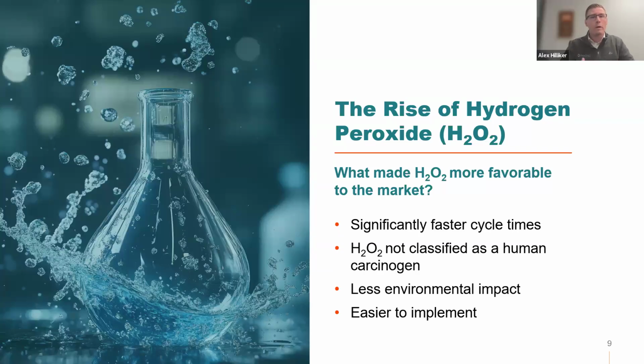And so, people may wonder what made hydrogen peroxide a more favorable option to ethylene oxide. First and foremost, one thing we always like to point out is that cycle time really matters here. With ethylene oxide, it used to take 8, 10, 12 hours to sterilize one load. And that's because of all of the requirements that were put in place for ETO. You've got a precondition, you sterilize, you aerate. That took a really long time. Today, with modern H₂O₂, vaporized H₂O₂ and H₂O₂ gas plasma machines, you can do those same sterilization cycles in less than 30 minutes. So huge increase in efficiency with that decreased cycle time, moving from ethylene oxide to hydrogen peroxide.